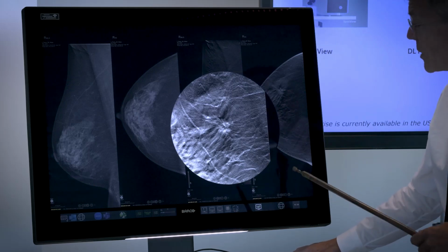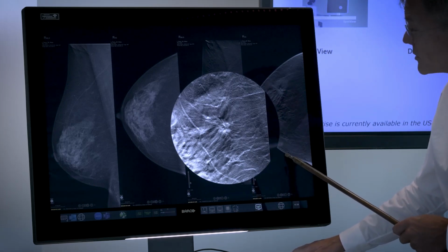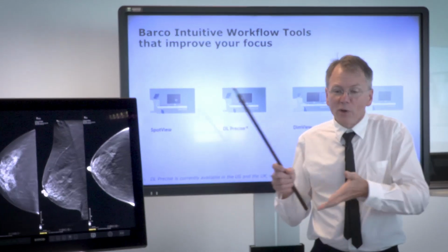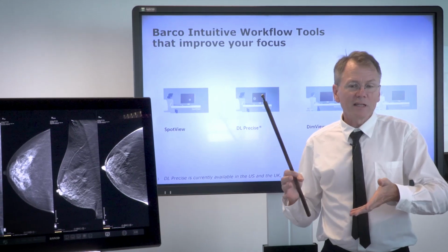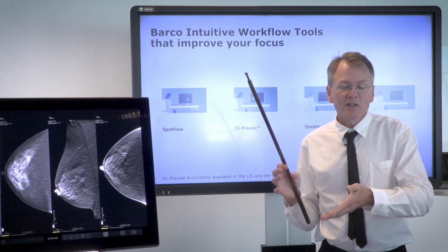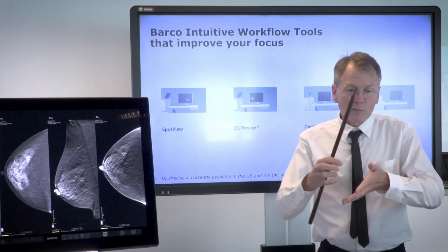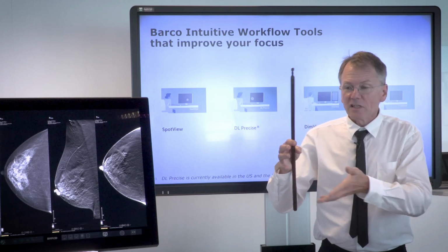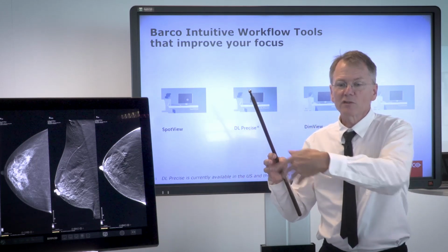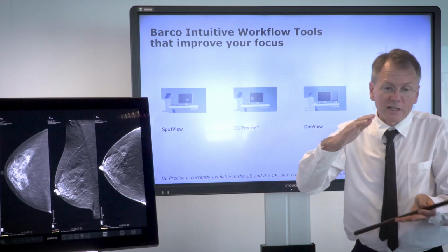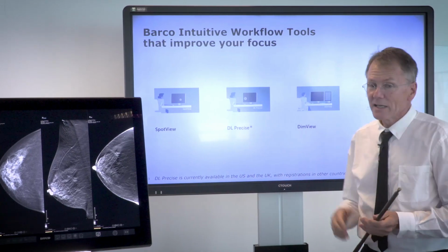So this is a very popular product, and I think one of the nice things about this being included with the Coronis OneLook is that the resolution here is always including all of the image that was acquired by the detector. And so when you're zooming that up, you're making it larger, but it's not like there's actually more resolution somewhere that you should be switching to. It's already all there on the screen, and we're just increasing the size of that 2x to make it easier on your eye.